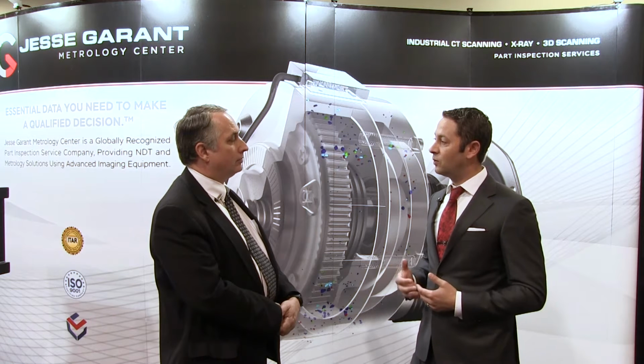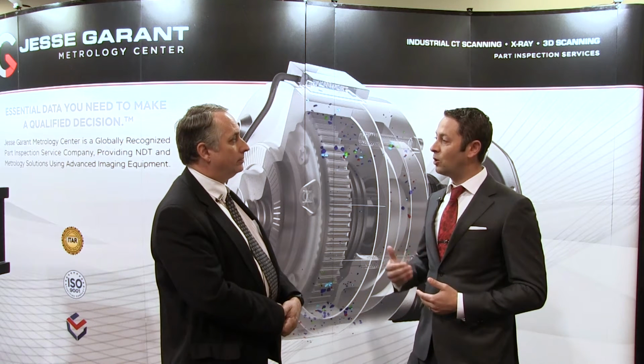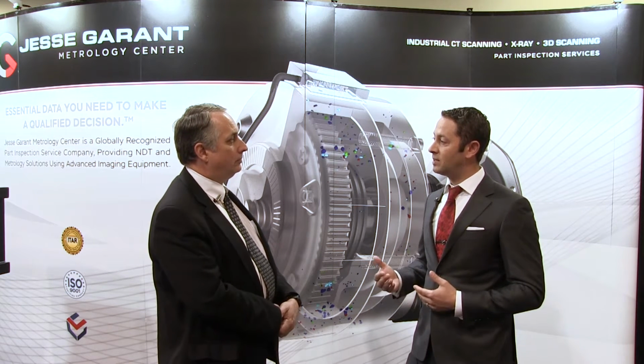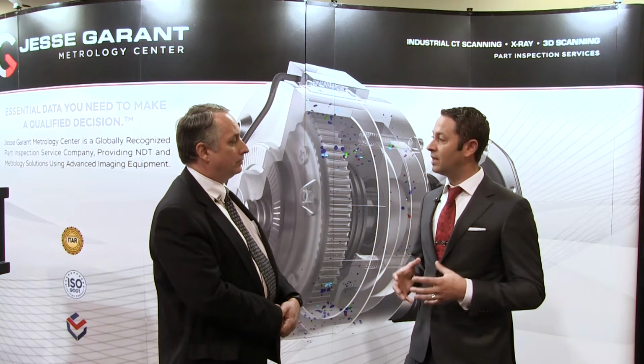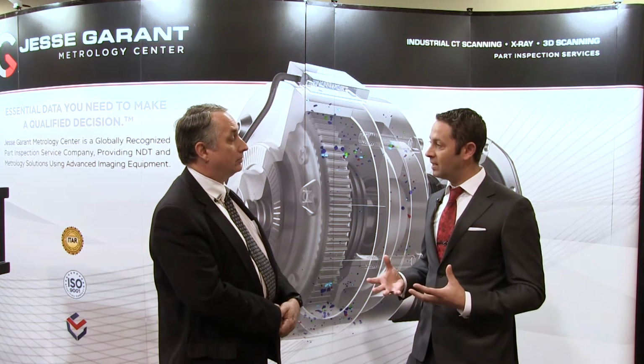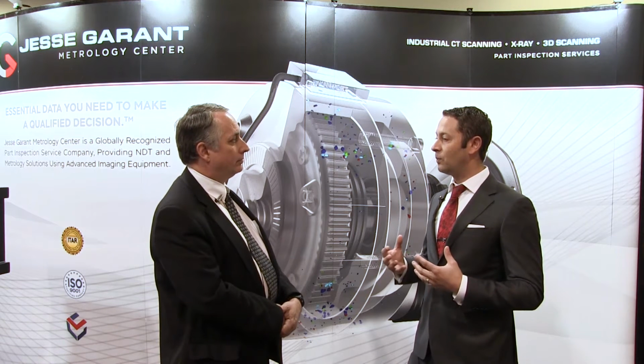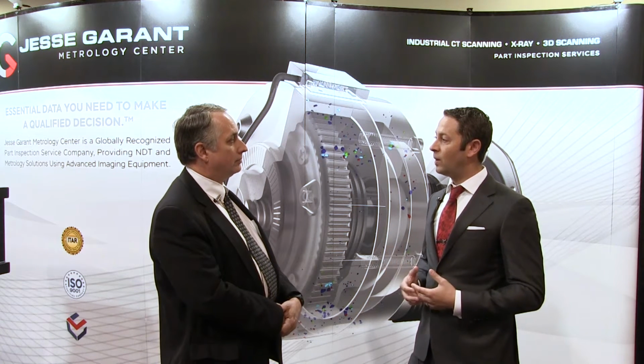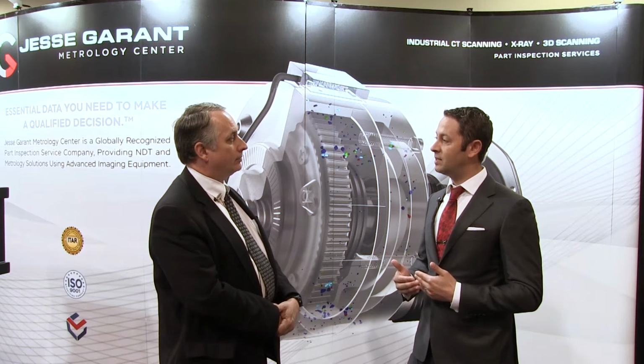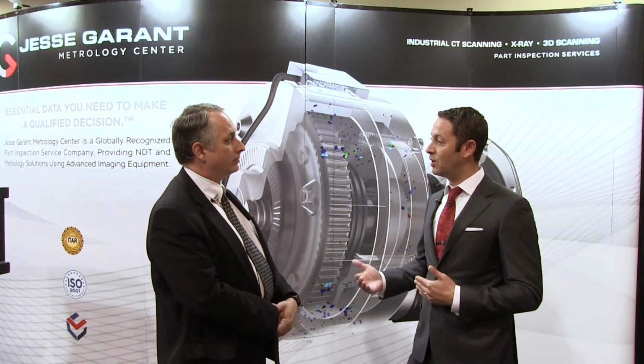Higher energy, accelerator-based CT was a very slow and very difficult process to use for additive parts. It would take almost half a day for scanning. It was very poor resolution, and it wasn't really a feasible technology when the inspection process is approximately 1/3 the cost of the part itself.